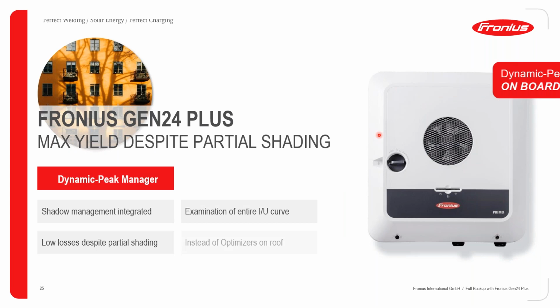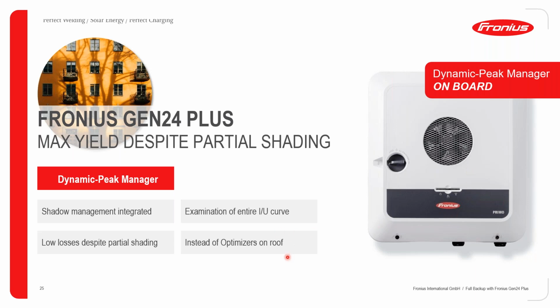Okay, then moving on, each Gen24 Plus comes with the Dynamic Peak Manager, and the Dynamic Peak Manager really allows you to install the system where you have a lot of partial shading happening. So the Dynamic Peak Manager is an integrated optimizer based on a software level that will send instructions to the hardware that's incorporated in the Fronius Gen24 Plus in order to change the voltage and current levels that are coming from the panels. And this will ensure that we can achieve the best power operating point throughout the day. And this will assist you in combating system derating, which usually happens whenever you have partial shading on your panels.